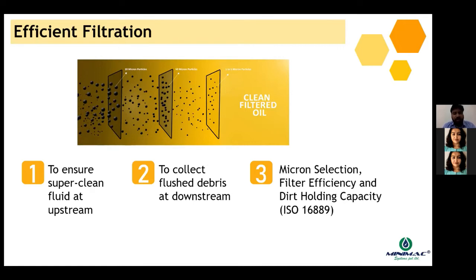So to ensure a super clean fluid on the upstream of flushing, or the flushing loop, you need to have stage-wise filtration after the downstream of the flushing loop. You need to collect it efficiently. By the term efficiently, what we mean is you need to have stage-wise filtration for the debris, wherein you can have a coarse stage as the first stage, a medium filtration at the middle stage, and a very fine filtration on the third stage, which would ensure that you have better life of your filters and at the same time a very cost effective filtration for your flushing loop.